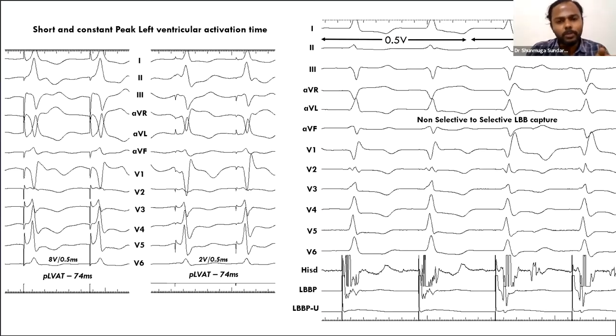This is how we usually perform PVC-guided left bundle branch pacing. Once you reach the target zone, you'll be able to show all the criteria of left bundle branch capture: short and constant peak LVAT, where at both 8 volt and 2 volt the LVAT is 74 milliseconds. You can even show non-selective to selective LV capture by observing the local electrograms from the lead tip. In non-selective capture, you'll see a pacing artifact immediately followed by the local ventricular electrogram. Once the output reaches near threshold value, you'll see a distinct isoelectric interval from the pacing artifact to the local ventricular electrogram.